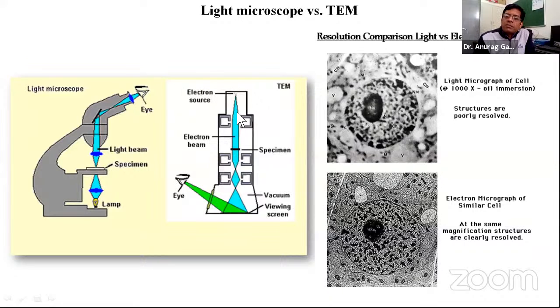Similarly, we use the same principle in transmission electron microscopy. Here is the electron source, that is the electron gun. That gun will emit the electrons. Then these electrons come into the form of a beam by applying accelerating voltage. Then with the help of electromagnetic lenses, this beam is focused. After focusing, the beam passes through the specimen. It transmits through the specimen. And these transmitted electrons, with the help of the objective lens, we can generate their image. The projector lens is also there. We can switch to get either the imaging formation or the diffraction formation, and then this image is projected over this fluorescent screen. So the image will be on this screen, and you can watch it with your eyes, or you can capture this image.